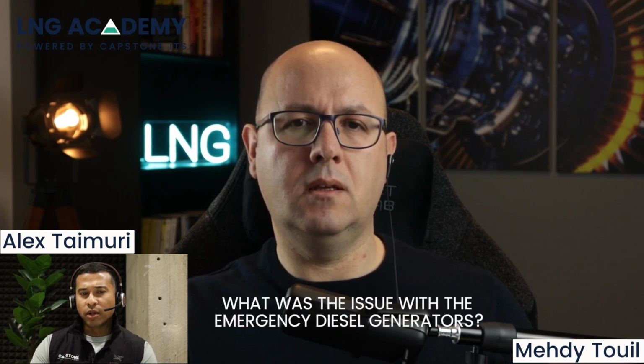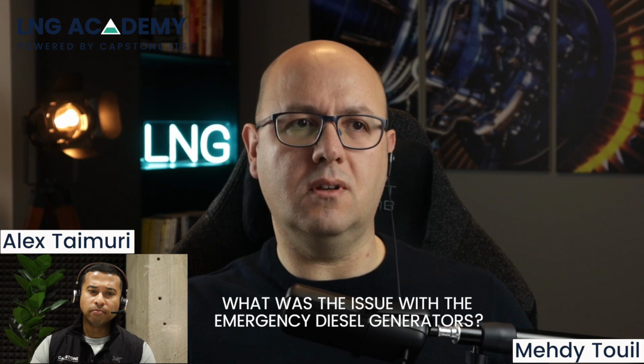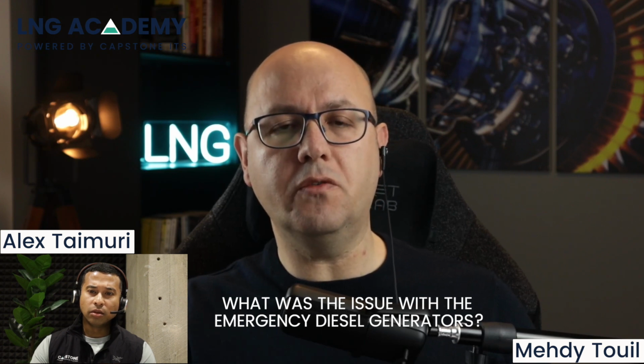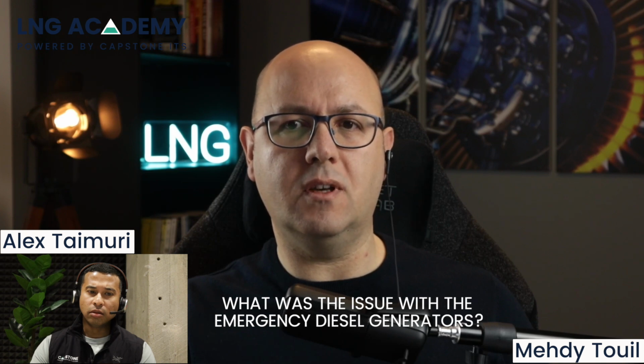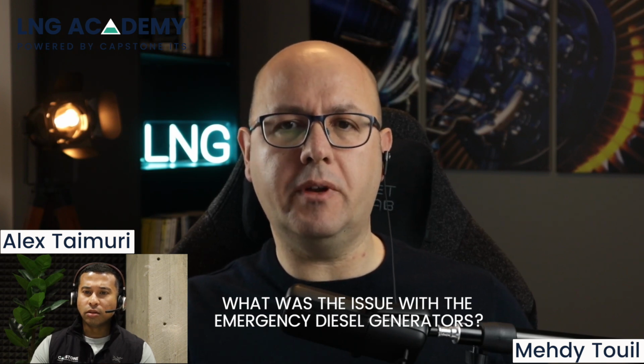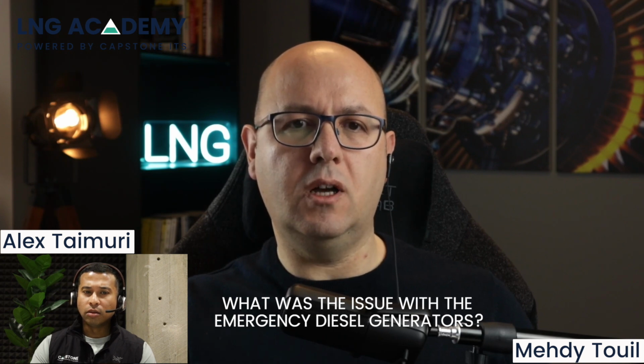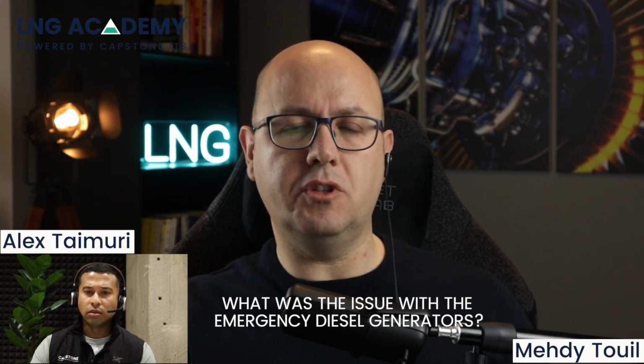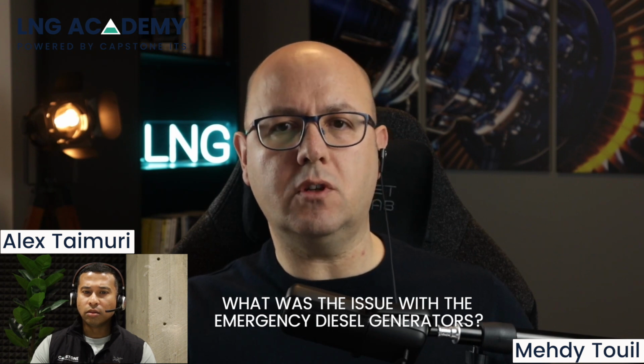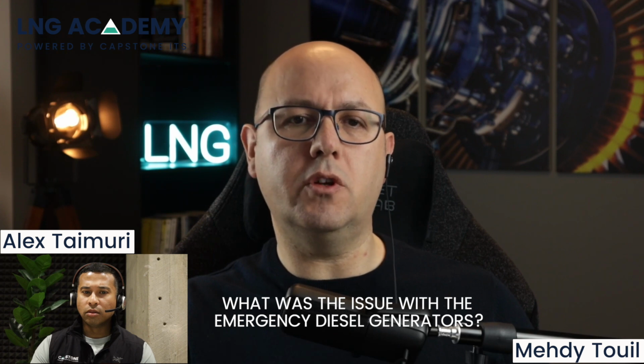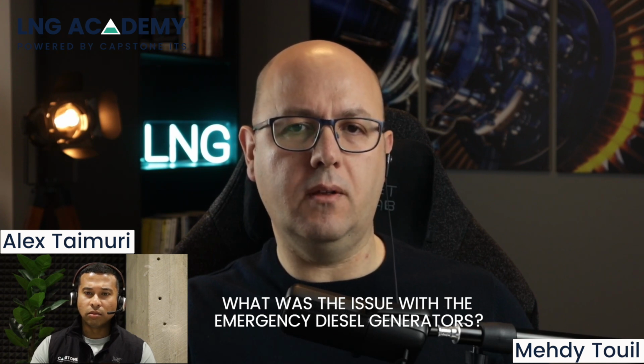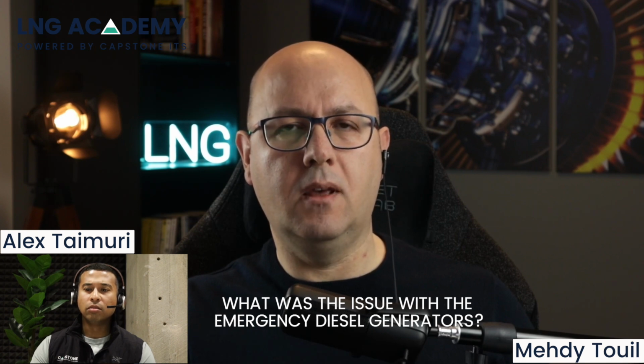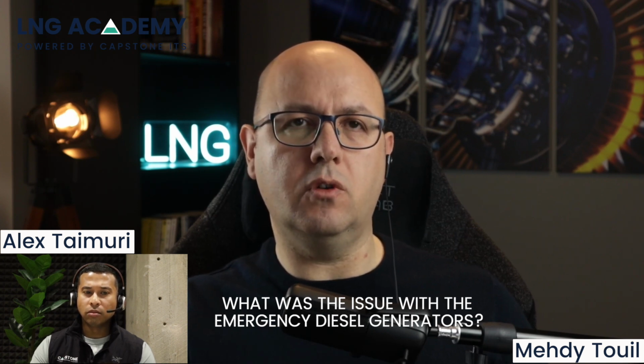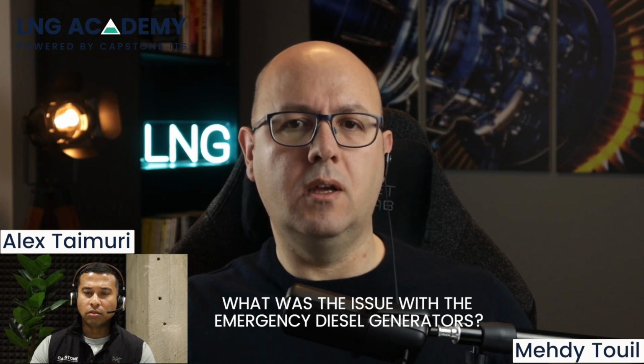What was the issue with the emergency diesel generators? Yeah, that was one of the most significant issues. So I couldn't find any official report, but from what I've heard from inside the industry, a high bearing temperature resulting from an excessive load tripped one EDG, one generator, and upon trip the load was automatically transferred to the other EDG, and that one could not sustain the excessive load as well, leading to a loss of emergency power. The high bearing temperature was attributed to a restricted cooling water flow. I suppose that the issue was rectified during the long maintenance period.